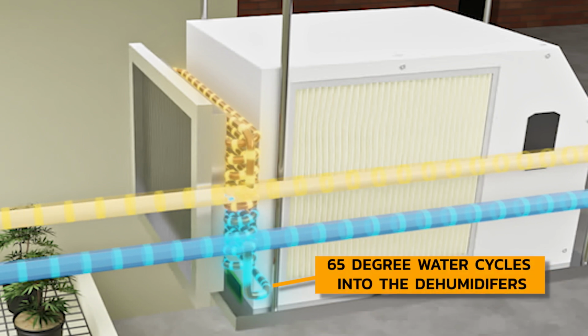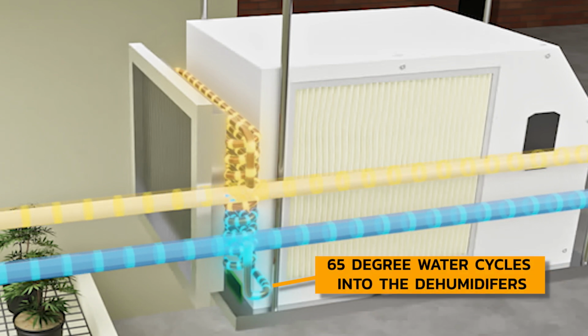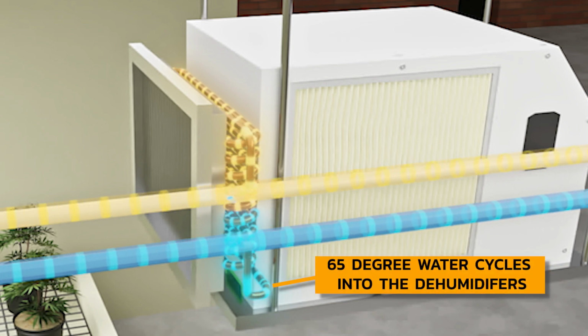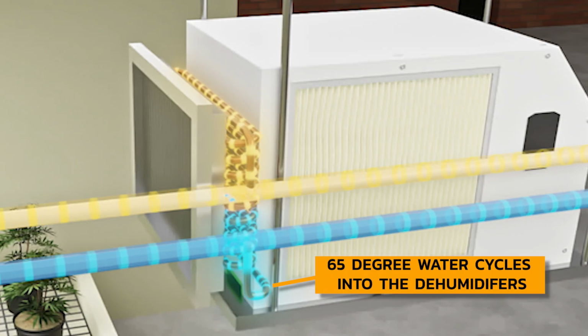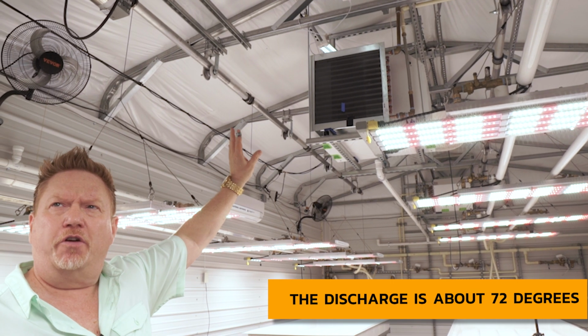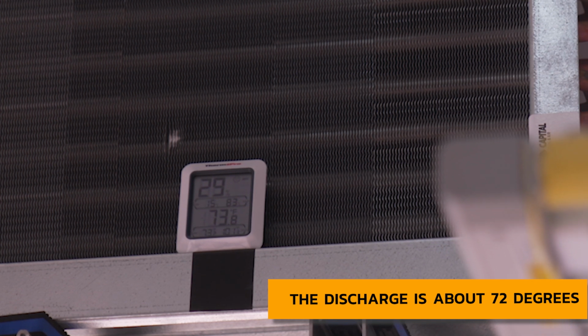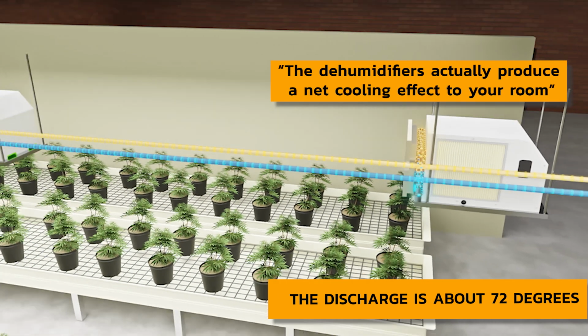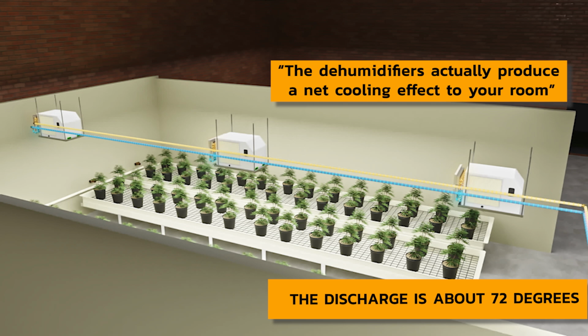We have 65-degree water coming in at the bottom of the coil, going through, picking up about 7 degrees across that coil. Discharge on this unit is about 72 degrees. Which normally would be 110. 110, so massive heat reduction on the dehumidifiers. The dehumidifiers actually produce a net cooling effect to your room, so when the dehumidifier is running, lowering the humidity set point, at the same time you're getting a cooling effect.